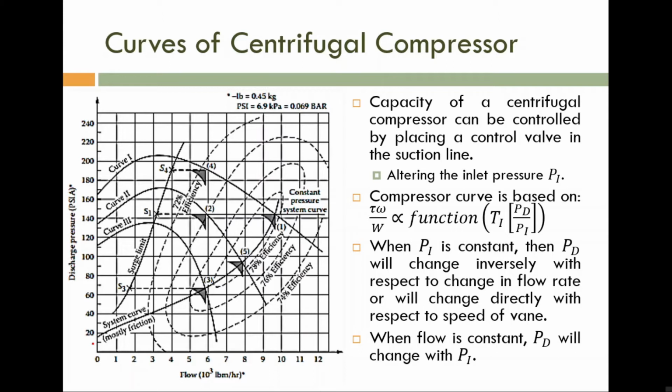That is one purpose. The second purpose is that the compressor is used to transport gas from one point to another. At that point there is no need to maintain a constant discharge pressure. We need to maintain a particular pressure that is sufficient to overcome the system friction. So two different applications are there: the first is maintaining a constant, high discharge pressure, and the second is achieving the flow rate.